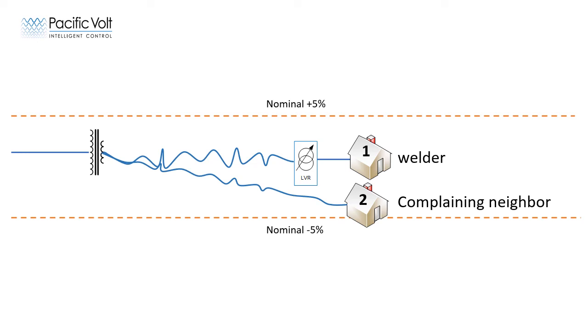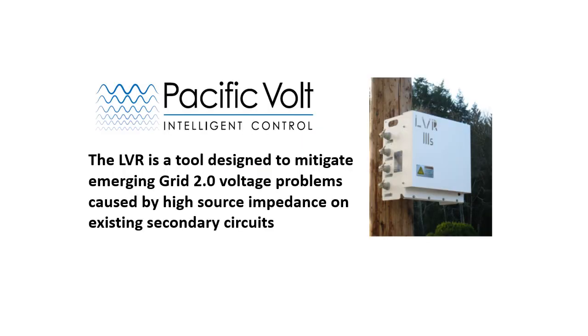The traditional fix would be to put them on separate transformers or one larger transformer to lower the impedance in an attempt to reduce the voltage fluctuations to an acceptable level. Keep in mind that an LVR does not change the actual impedance of the secondary. Only installing a larger transformer and conductors can change the circuit impedance. However, the LVR effectively reduces the impedance to nearly zero because of its bidirectional line drop compensation and subcycle regulation.